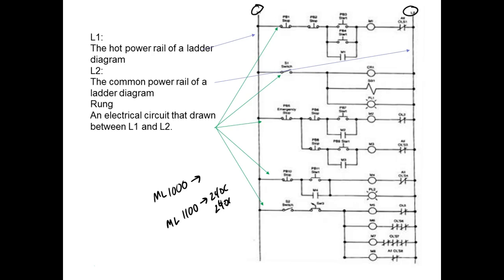If you, so we call this L1, but when you look in industry, it's probably going to have more added to it. So you differentiate between the three-phase power applied before the transformer and what goes on after the transformer. That makes sense, so we'll do that in motor controls, and somebody will hook us up over here to L1, L2 on the 208 volt side. And if we were to apply power on it, it would just burn everything up, right?